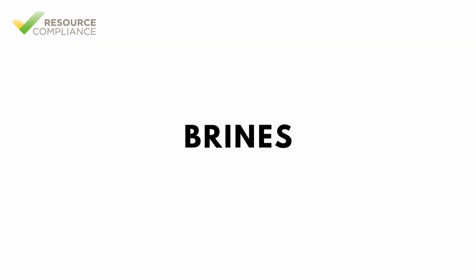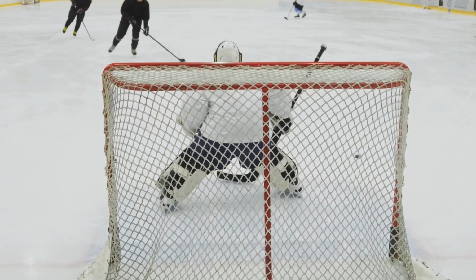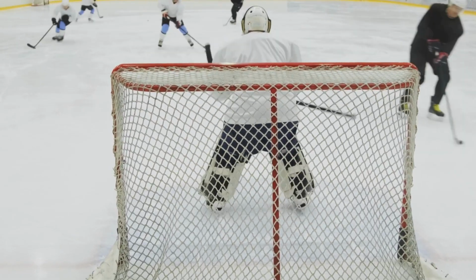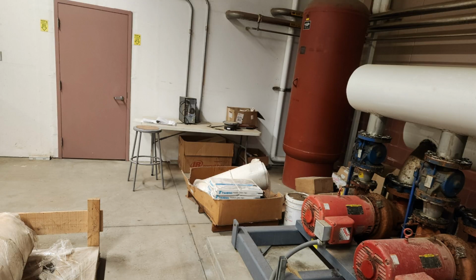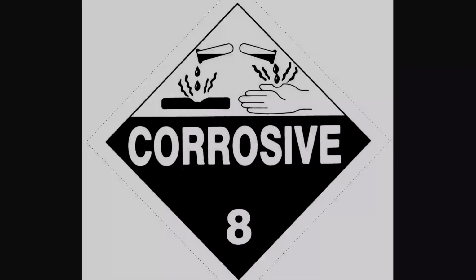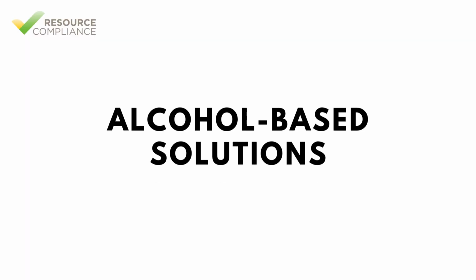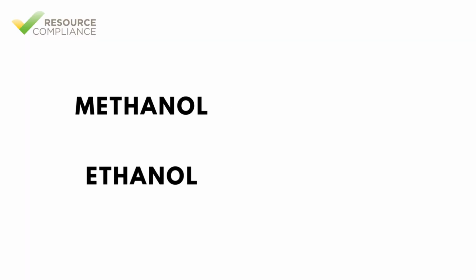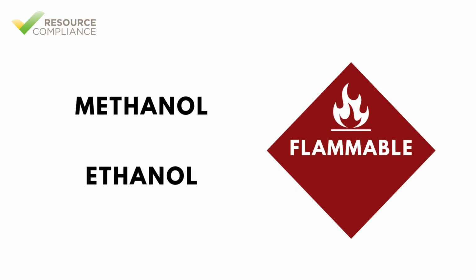Brine solutions such as calcium chloride or sodium chloride are used in applications requiring low operating temperatures. These solutions have good thermal properties and can remain liquid at sub-zero temperatures, making them suitable for cold storage and ice rink cooling systems. Brine solutions are attractive because they are inexpensive, but carry the downside that they are corrosive and must be handled with care. Alcohols like methanol or ethanol can be used as secondary coolants, particularly in applications requiring temperatures below -40 degrees Fahrenheit. However, these solutions can be flammable and may require additional safety measures.